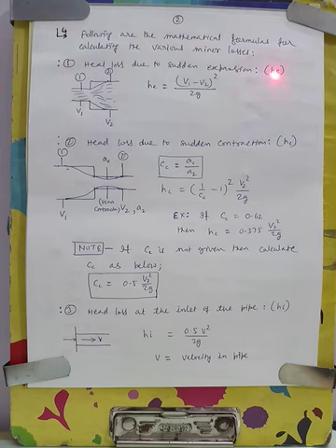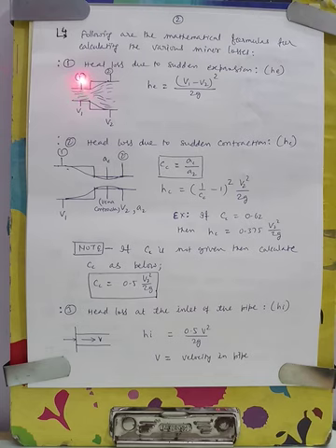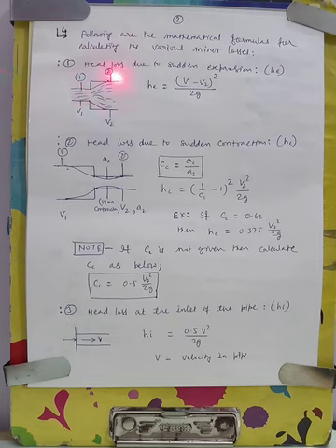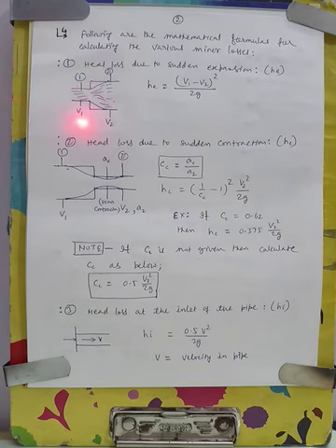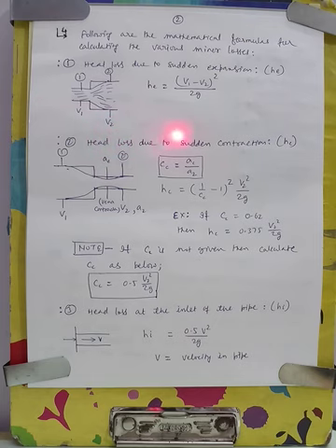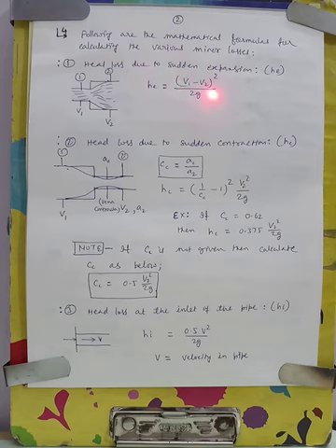Number one: head loss due to sudden expansion, h subscript e. Suppose this is the small pipe — section one — and section two is of the bigger pipe. After this small pipe, there is a fitting of a big pipe. When the fluid enters from this pipe to this pipe, there will be sudden expansion. Suppose in the small pipe the velocity of fluid is V1, and in the bigger pipe the velocity of fluid is V2. Then we can calculate the head loss due to sudden expansion as: h_e = (V1 − V2)² / 2g, where g is the acceleration due to gravity.